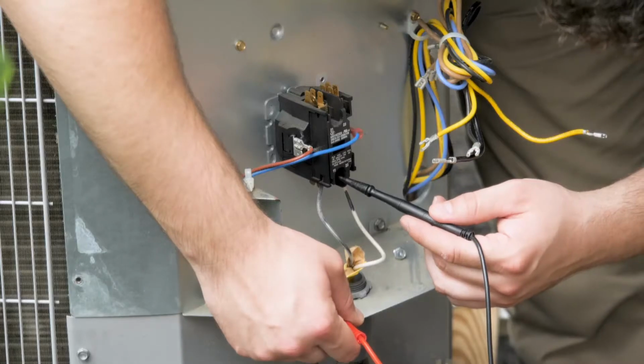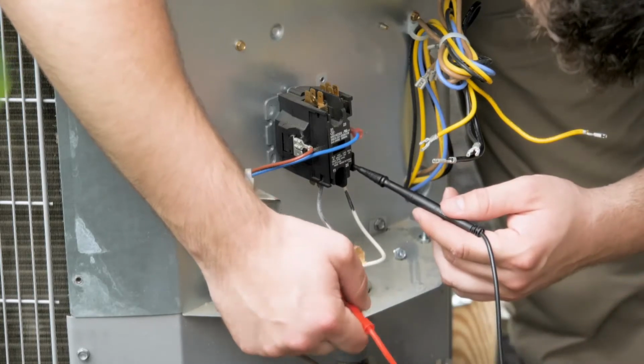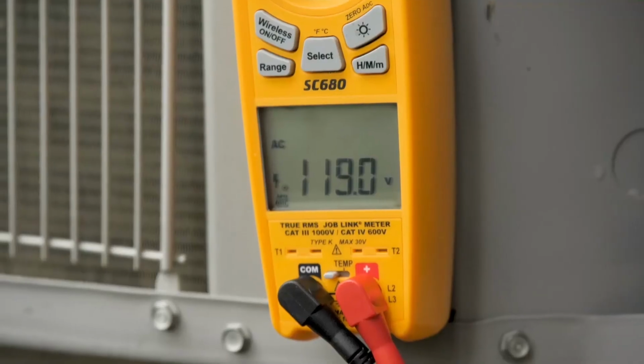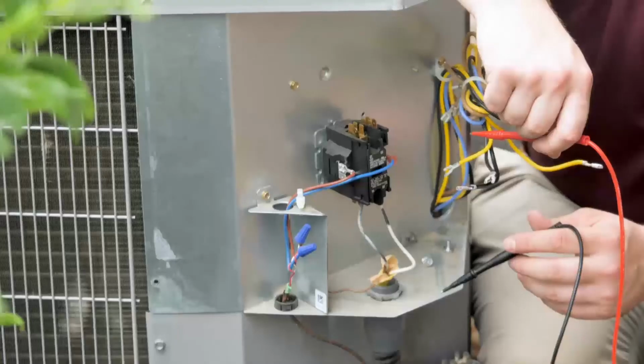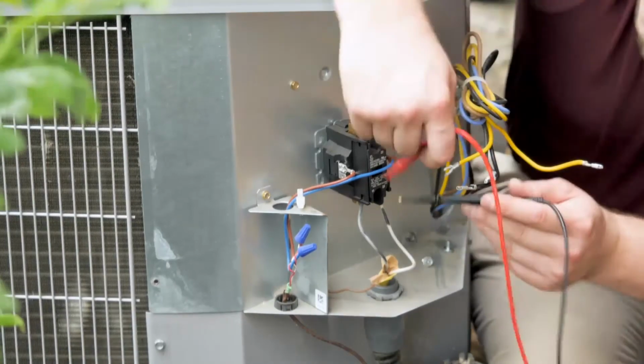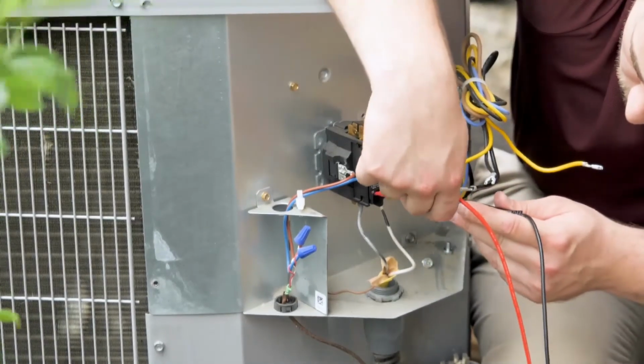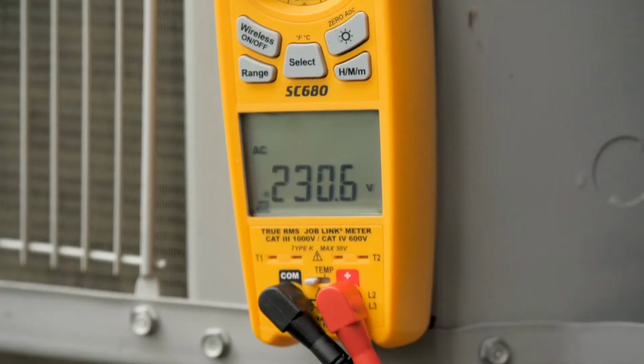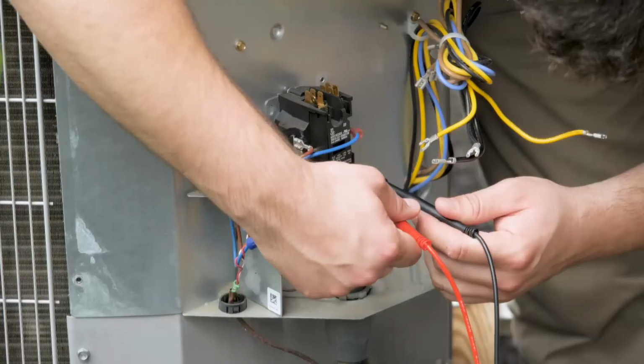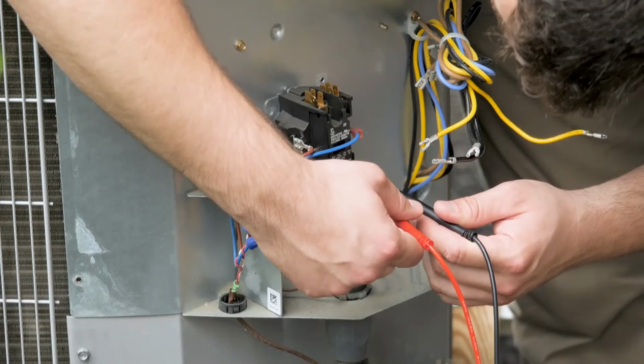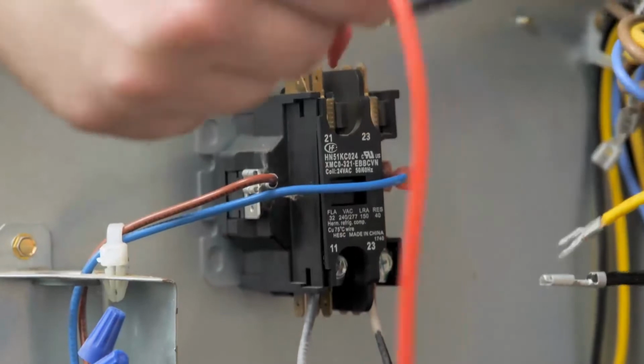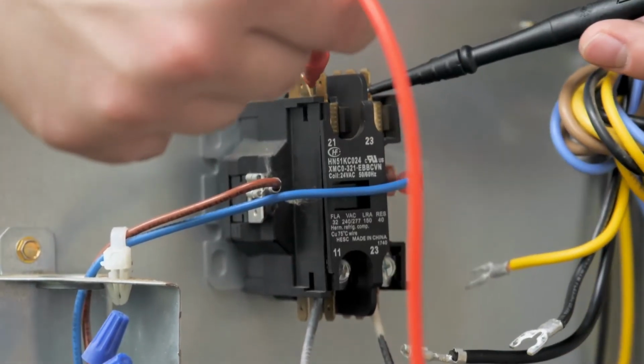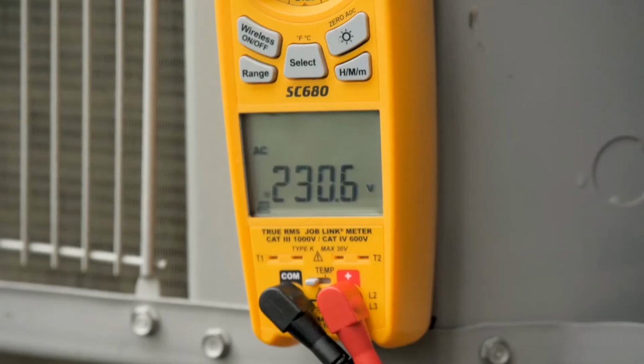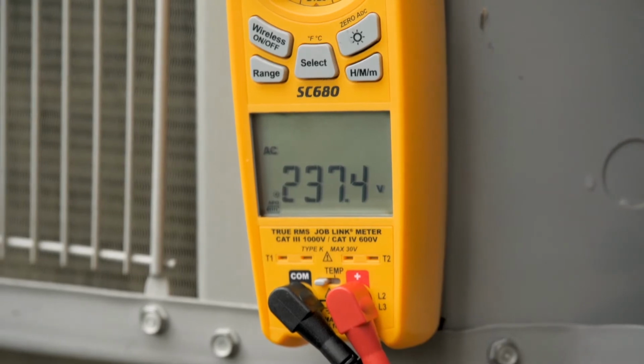Next, take the meter lead and place it on L2 to ground. You should also have 120 volts on your screen. And we'll check power from line 1 to line 2. This should be approximately 240 volts. Now we're going to come up through to the top two screws, or the top two points where we took the screws out. We're going to test there. We should still have the same 238.